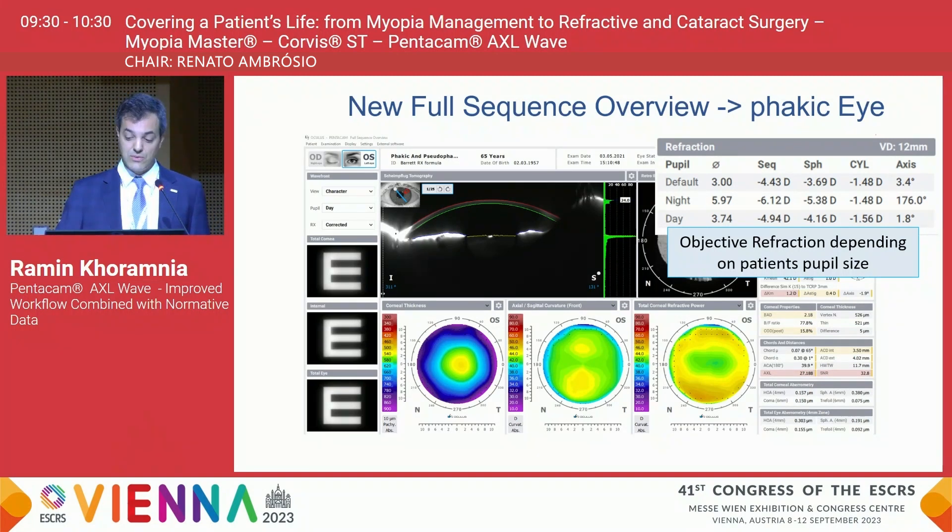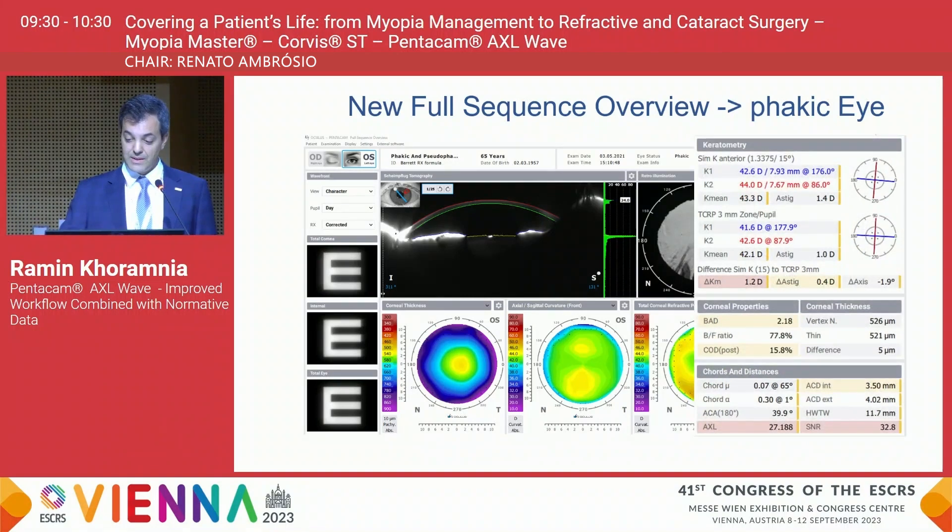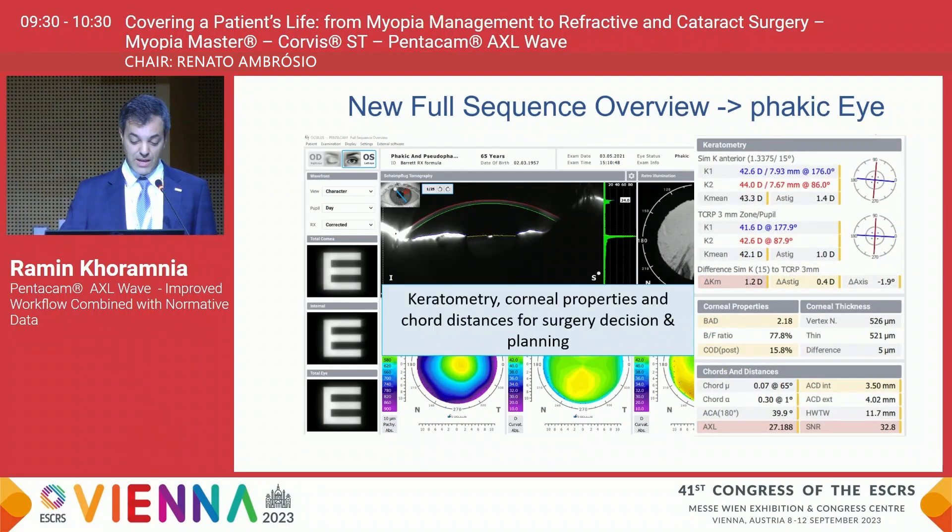The retro illumination image is very nice to show the patient and demonstrate how they are suffering from a cataract, and after surgery you can also visualize the intraocular lens that has been implanted — for example, you can see the toric markings and use the device to check the right axis. The device also gives a lot of information on keratometry, corneal properties, and chord distances, which is very important when it comes to surgery decision and planning.